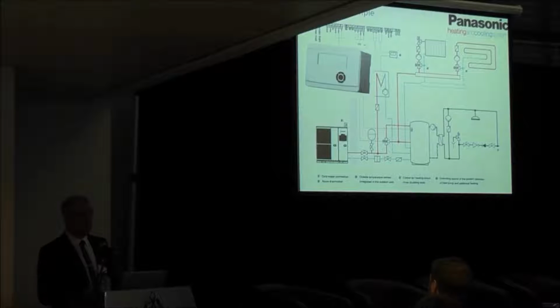Based on the electrical supply to the house, they might not be able to. In a very large house, for instance, they may need 2 heat pumps, but the electrical supply to the house might not allow them to run 2 heat pumps. They install 1 heat pump, they install a bivalent, and they keep their existing boiler.